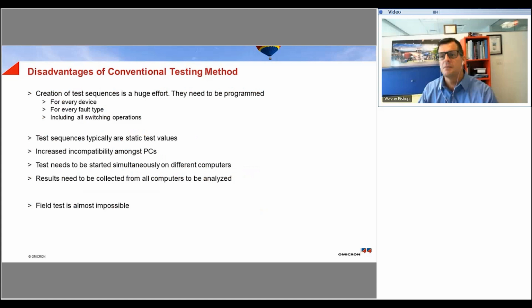Tests under real-life conditions require the test values to match those of real-life faults as closely as possible. The method of testing that we described here uses static fault values, which are typically applied, and then the resulting reaction from the Recloser is measured. Under realistic cases, a DC offset is typically present, and depending on the algorithms of each Recloser control, one device in the scheme might detect the fault faster than another. So in order to determine the real performance of the scheme, it's always beneficial to test with transient signals.